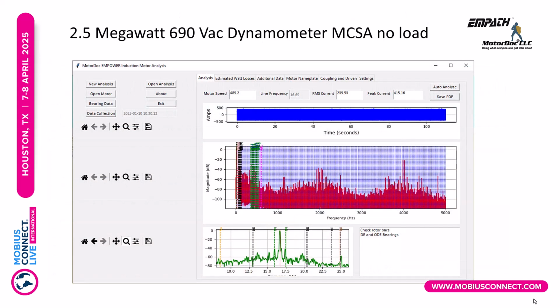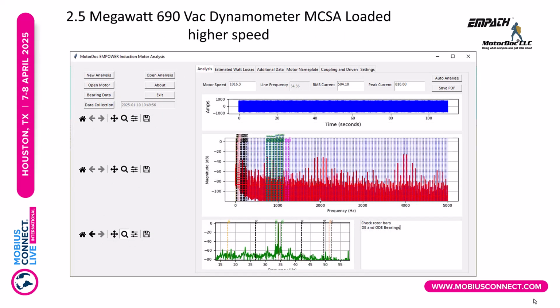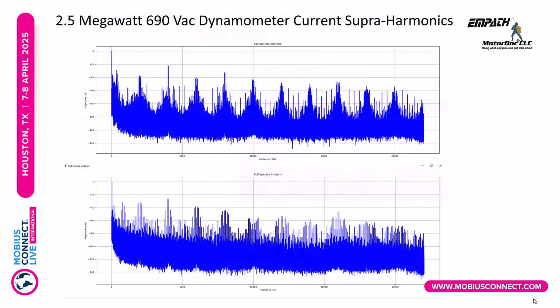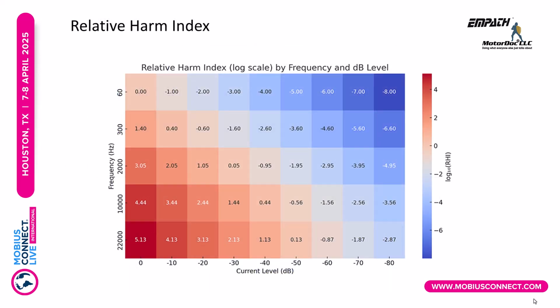Okay, you can see that in both cases. And then this is at the higher speed and under load. But we also looked, and the reason we did current signature is because this particular system is designed to look at supra-harmonics. That's harmonics greater than 2 kilohertz and under 150 kilohertz. And out here you can see where those frequencies are very high. Well, what happens, we'll talk about that in a second, because they did have a shaft brush on here, but it was basically bypassed because of the high frequency noise, because they didn't filter the output.